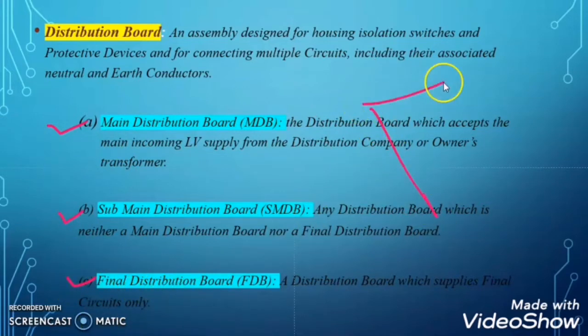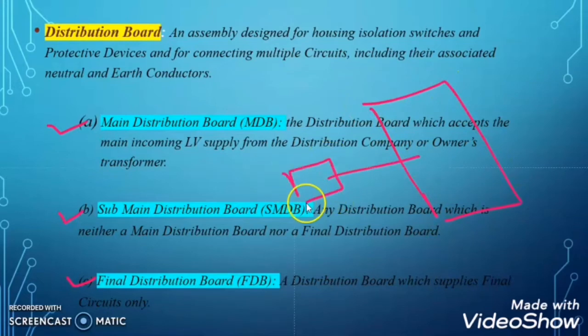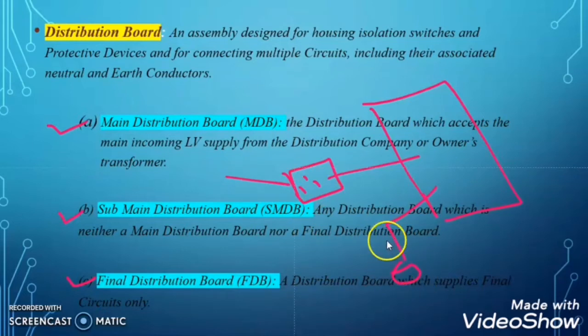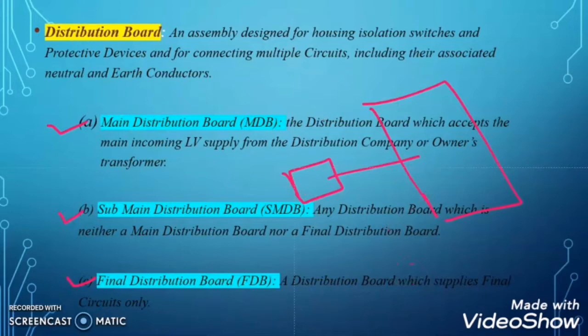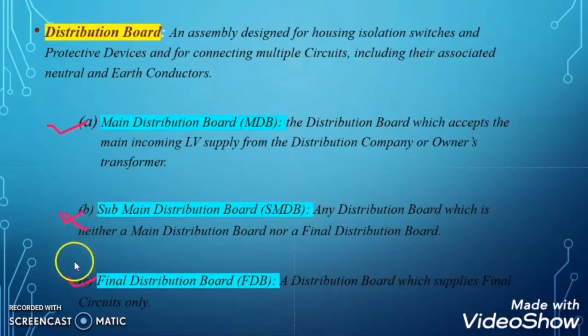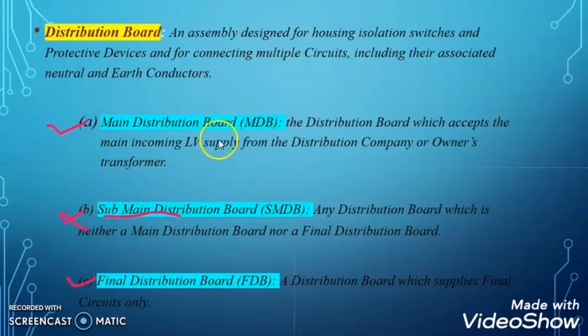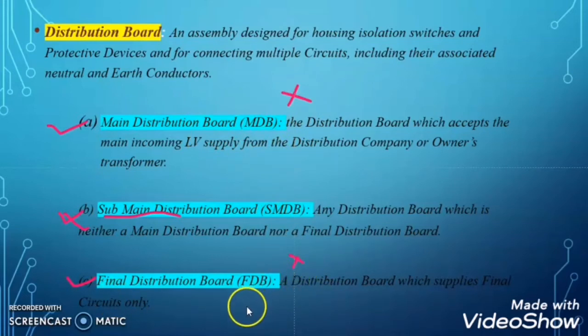Any distribution board is said to be a final distribution board when it is directly feeding the final circuits like sockets, lights, or any other power utility like washing machines or water heaters — directly to the final equipment. Any distribution board is said to be a sub-main distribution board when that distribution board is neither a main distribution board nor a final distribution board.